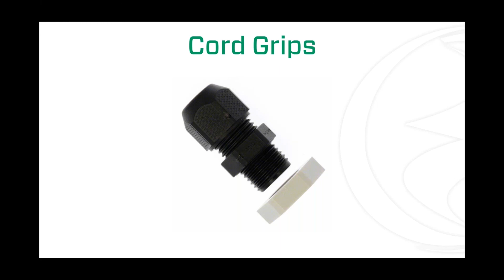That next item is a cord grip. These are vital in many applications, especially ones with junction boxes, and even more so if you have a junction box in a pit. A cord grip is simply a little plastic piece in this case, with a rubber bushing inside and a nut on the outside. As you tighten the nut, you compress that rubber bushing, and it compresses around the cord of whatever you're putting through it—pump power cord, float, sensor cable, whatever. It forms a good solid connection to keep moisture and gases out of the junction box.